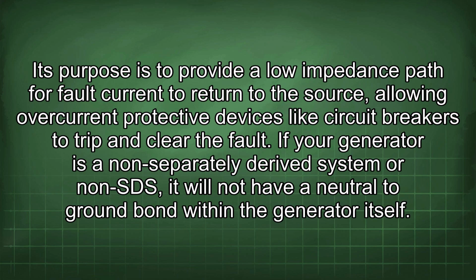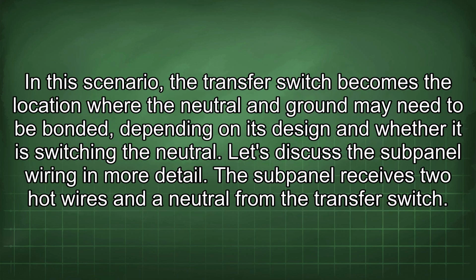If your generator is a non-separately derived system, or non-SDS, it will not have a neutral to ground bond within the generator itself. In this scenario, the transfer switch becomes the location where the neutral and ground may need to be bonded, depending on its design and whether it is switching the neutral.